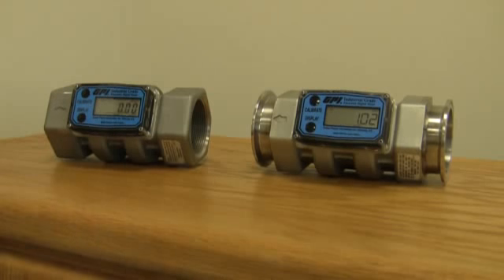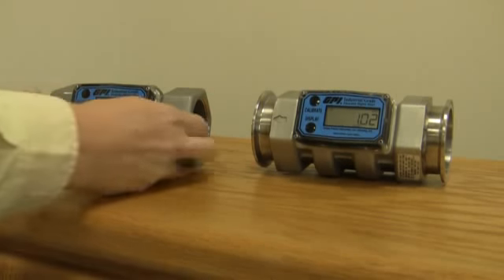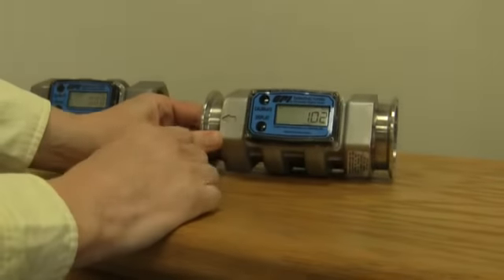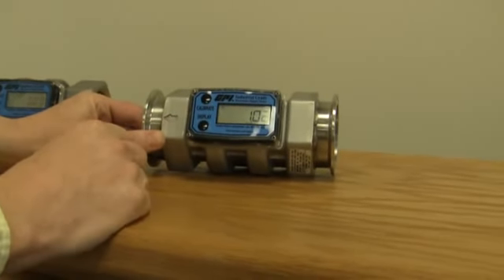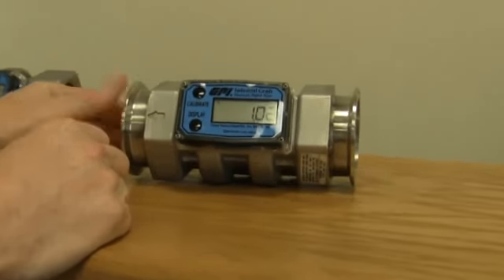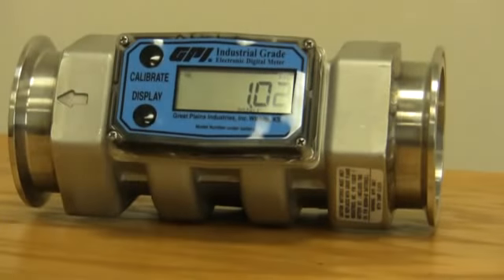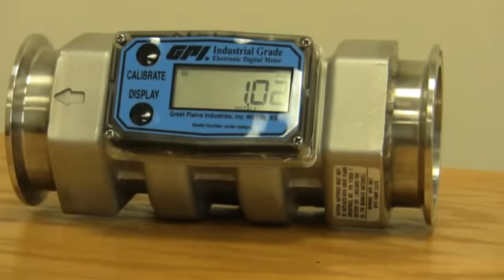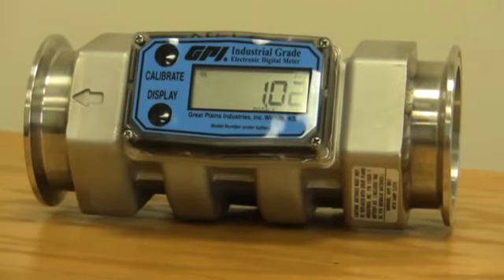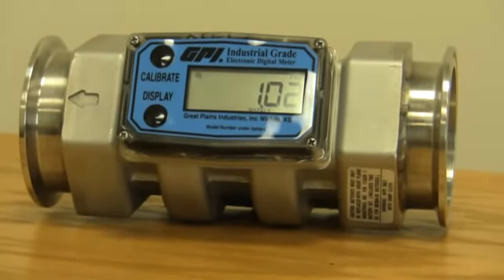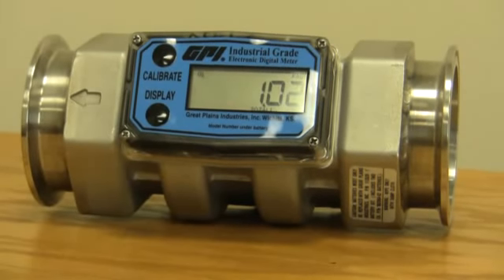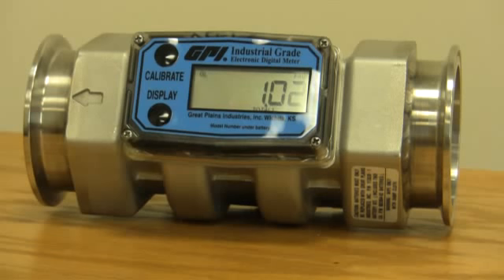Well, now we're going to talk about how to calibrate the new one. I'm going to get the old one a little bit out of the way. The new one, first of all, why do you want to calibrate it? They come from the factory calibrated to the viscosity of water. So if you're running water or anything that pours like water, the factory calibration should be very accurate for you. But let's say you're putting something through it that's a little bit thicker, like antifreeze, and you want to calibrate it to that thicker fluid.